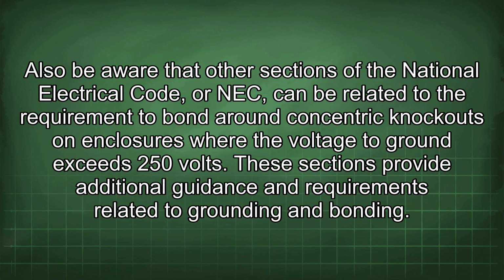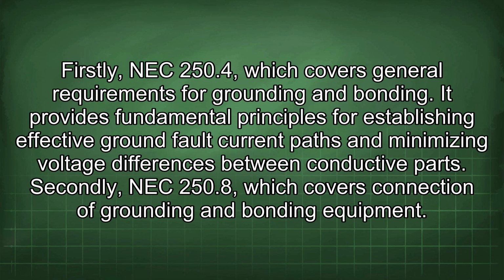Also be aware that other sections of the National Electrical Code, or NEC, can be related to the requirement to bond around concentric knockouts on enclosures where the voltage to ground exceeds 250 volts. These sections provide additional guidance and requirements related to grounding and bonding. Firstly, NEC 250.4, which covers general requirements for grounding and bonding. It provides fundamental principles for establishing effective ground fault current paths and minimizing voltage differences between conductive parts.